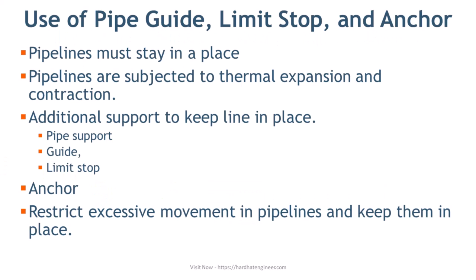Pipelines must stay in place where they are installed in the pipe rack. When temperature changes, metals are subjected to thermal expansion and contraction. So we need some additional support to achieve this functionality. Pipe supports such as guide, limit stop, and anchor keep the pipeline in place throughout the operation. They restrict excessive movement in a pipeline. Each of these has a unique function.